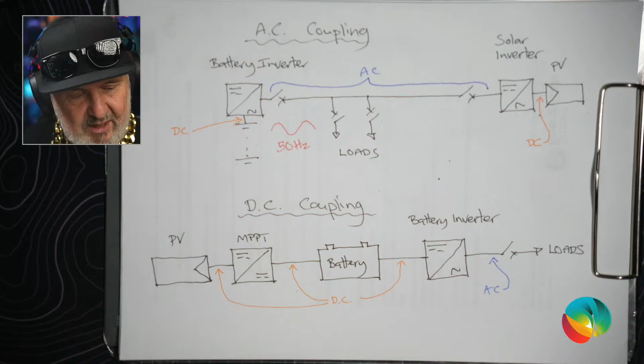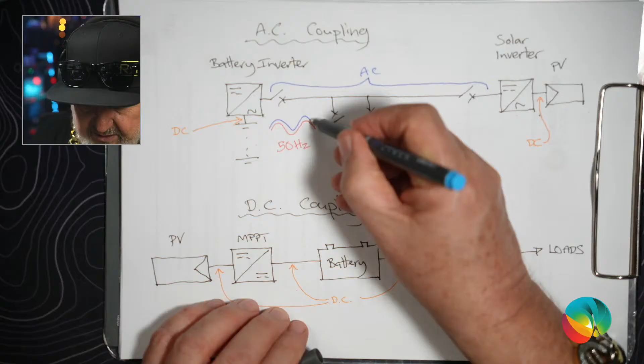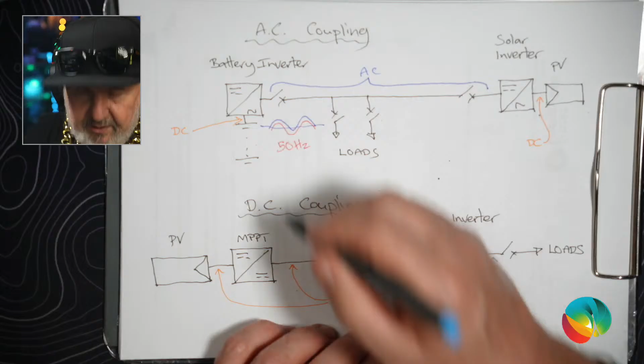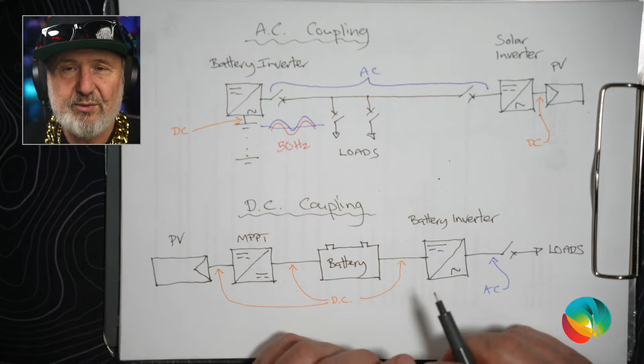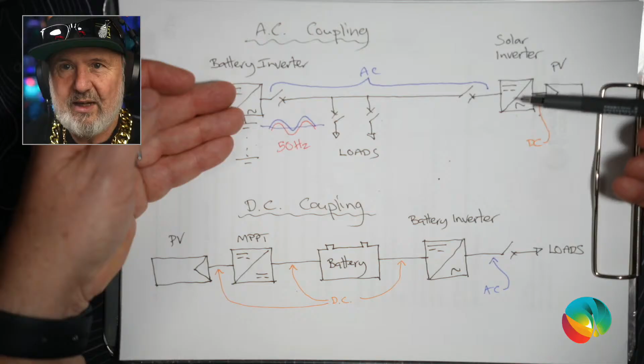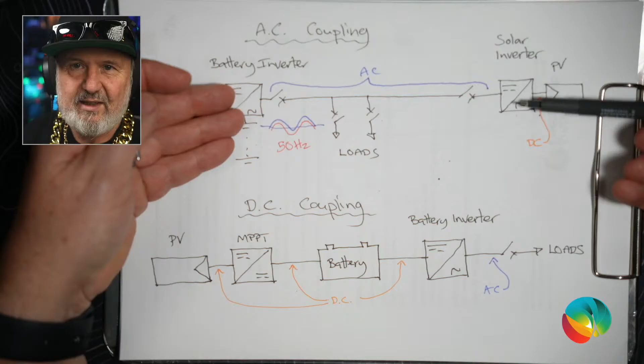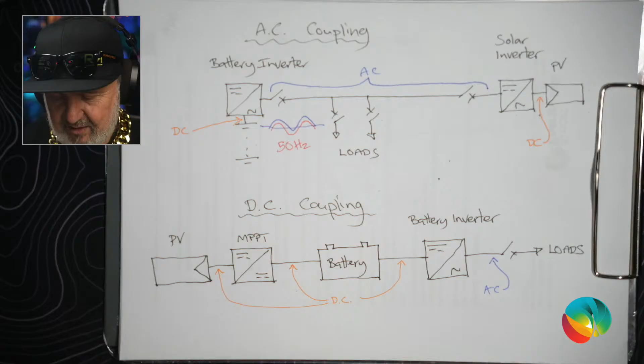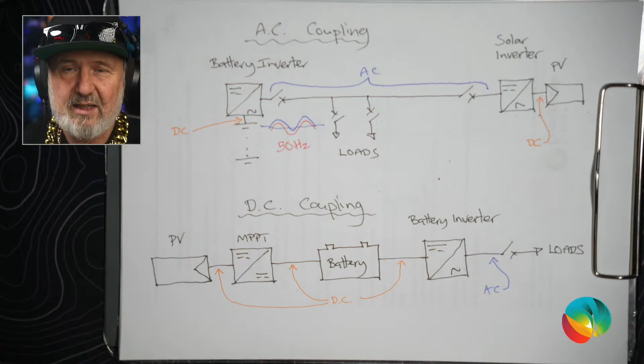So it's going to generate a 50 hertz perfectly in sync signal. So it'll create its own perfectly in sync signal like this. And at a zero crossing point where there is the least energy possible movement, it then will close its grid protection relay and parallel at that point. So at that point, these two sine waves are in parallel and working together. And by changing very slightly the phase angle, you can cause that current to flow. So the current will flow from the solar inverter to the loads first, and then any surplus to the battery inverter, the bidirectional, and charge the batteries.